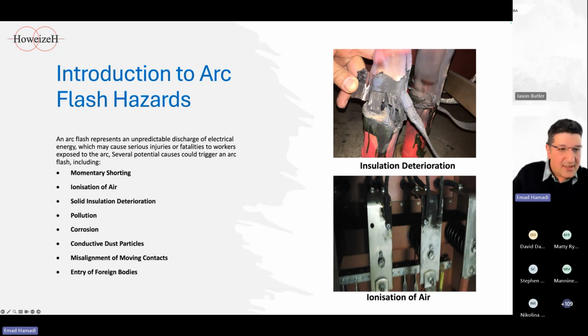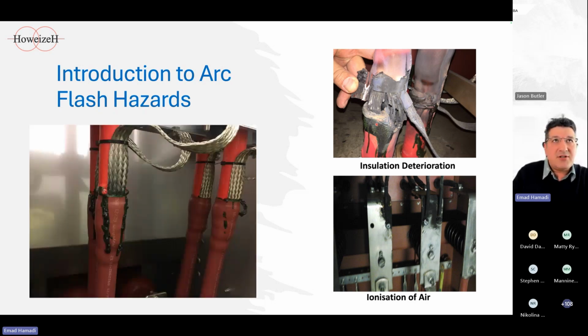Let me just turn on my laser. One of them, which tends to be less likely to happen, I would say, is ionization of the air, which, as you can see, is happening phase to phase. This is the compartment of the STG steam turbine generator, HV1, and it's quite a clean compartment, but this happened due to ionization. And that one is insulation deterioration that causes the arc flash.